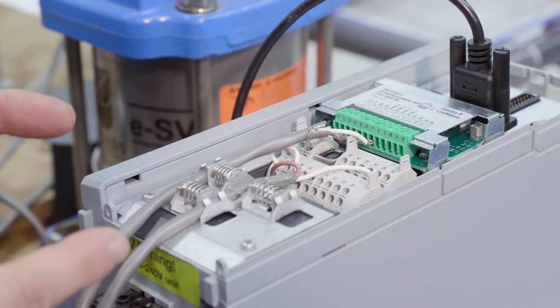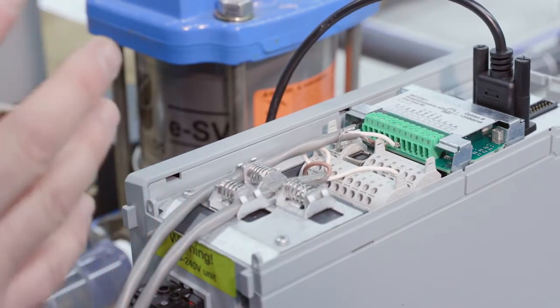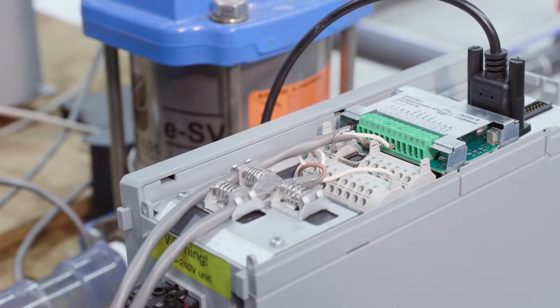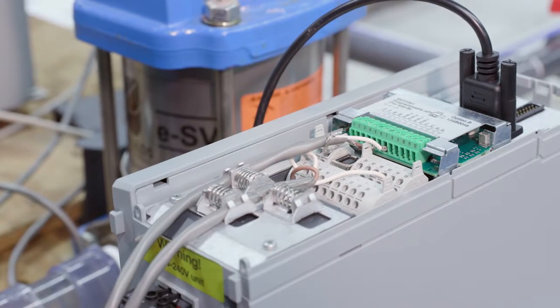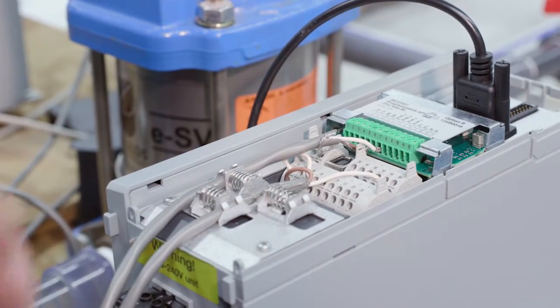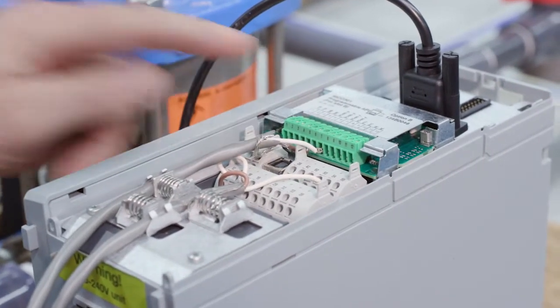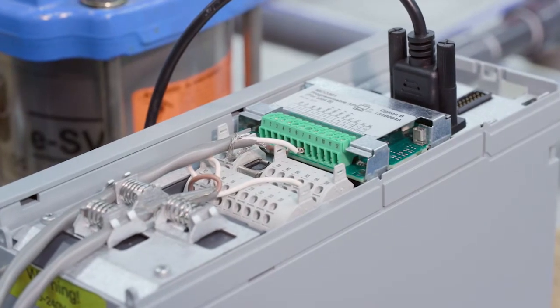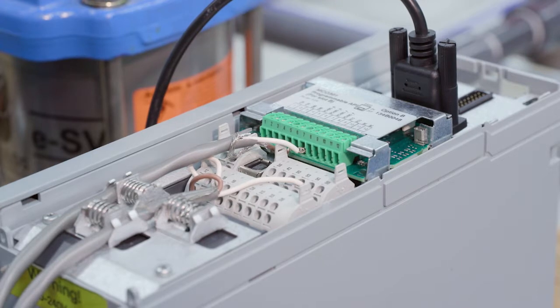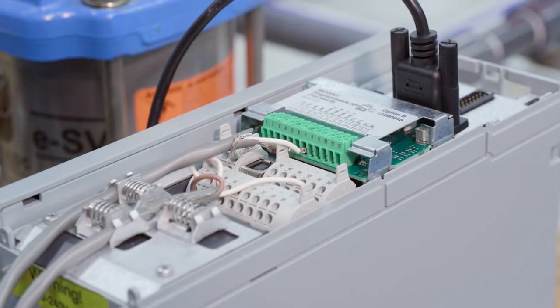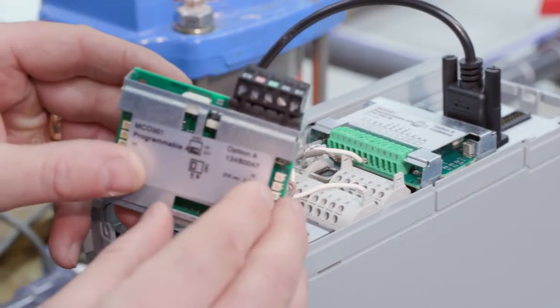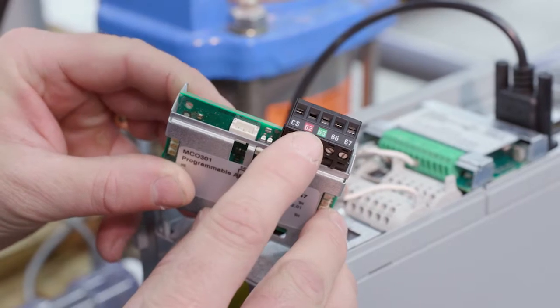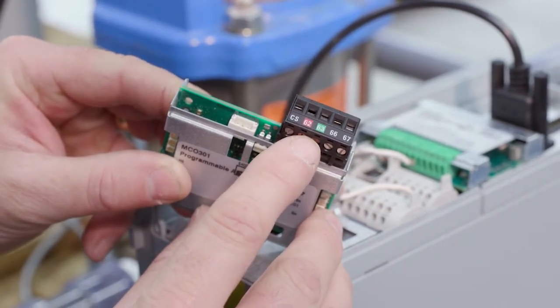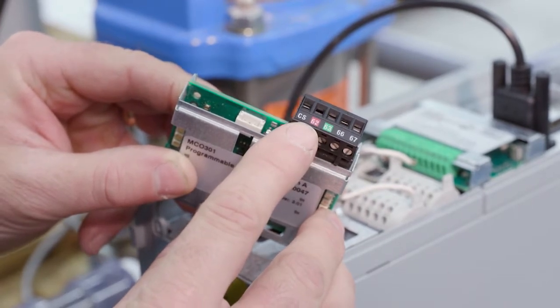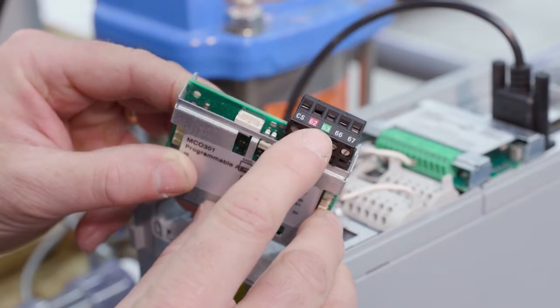One is multi-pump. Now you can go up to 4 pumps. So in the past with the basic you were limited to 2. With the advanced platform you can connect 4 pumps together in true lead lag fashion, and the wiring is much simpler now, and we're only talking about 2 wires between your MCO301 cards, and in this case your 66 and 67. With the B card, that is your RS485 ports, so it's only 2 wires compared to the wiring harness. Now, one thing to note, if you are using the optional A card here, the wiring is off the top and the terminals are different. If you are using this card with multi, you are going to connect 62 to 62 in the other pump or pumps, and then 63 to 63.